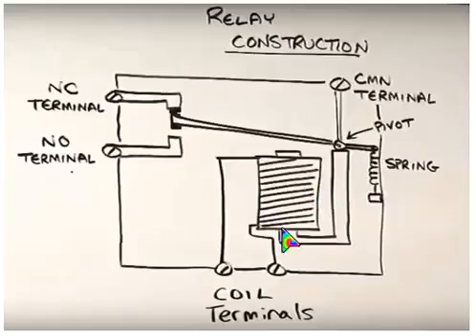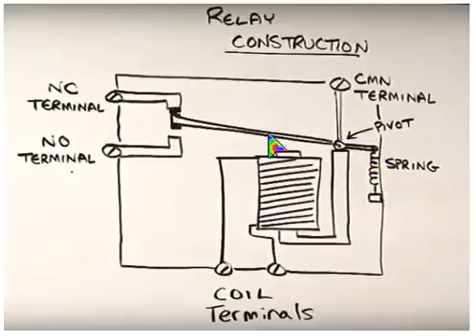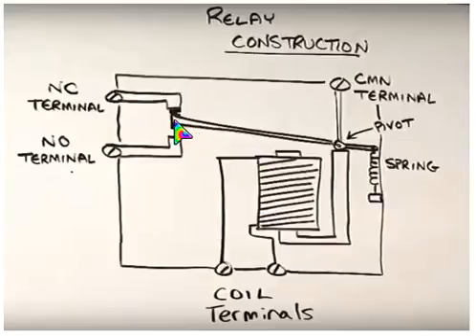In this picture you can see a relay construction. It has a few components: the magnetic coil, an NC terminal, a NO terminal, and a pivot. This pivot is connected to a common terminal with a metal object. The long object is the armature — basically copper or some very high conductive material. The other side of the pivot is connected with a spring, which is fixed to an object. So one side of the armature is fixed with the spring, and the other side is loose.